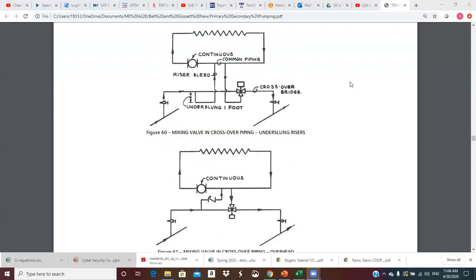The continuous flow established by primary-secondary arrangements has important advantages when secondary zones are to be separately reset, and is most especially advantageous for freeze protection of air handler coils. The freeze protection comes from continuously pumping, and also if you have control of airflow, you could keep the water temperature a little bit warmer.